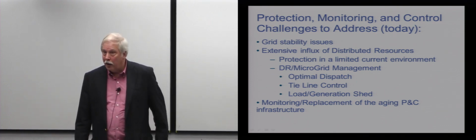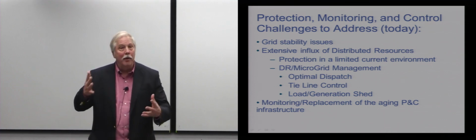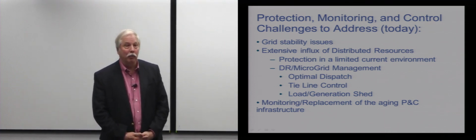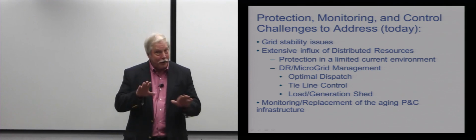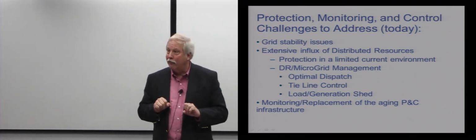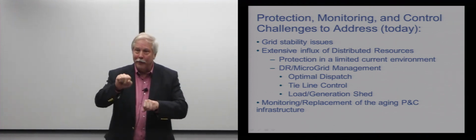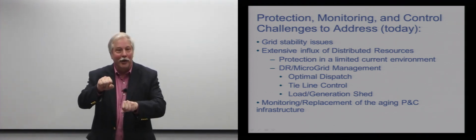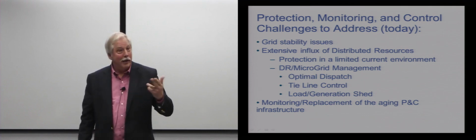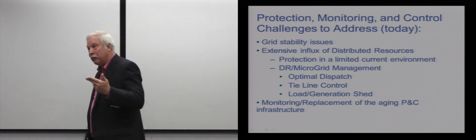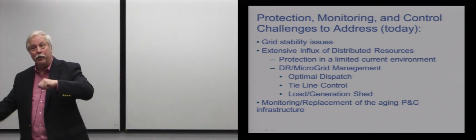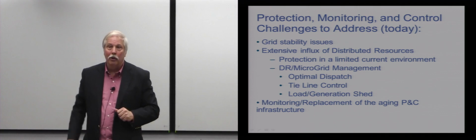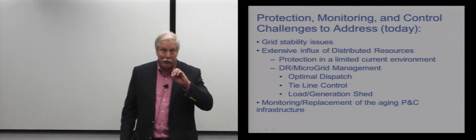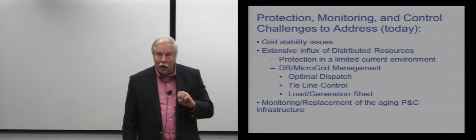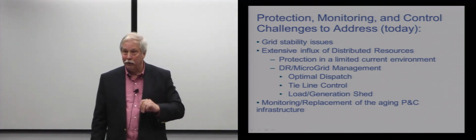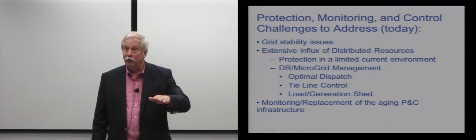Today we have some mechanisms in place. The best one is called under-frequency. In fact, under-frequency has a direct correlation to our fellow on the bicycle. As the person's going up the hill, he's going slower and slower. Same thing on the power system: as you try to push more power out, the frequency of the power grid starts going lower and lower. So an incipient detection element is under-frequency — you start to see the power frequency go down, something is wrong.